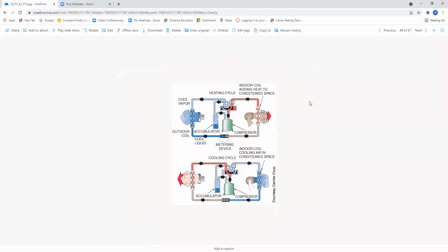Okay, in this position here, the top one shows what happens when this thing is running in the heating mode. Notice that the compressor is still going to run. Notice that heat pumps usually always have an accumulator. The idea behind the accumulator is to catch any liquid refrigerant, because we do not want this liquid refrigerant entering the compressor. Got that? We do not want liquid refrigerant entering the low side of this compressor. We have an accumulator to protect the compressor from liquid refrigerant. Notice that the discharge line, in this case, is always common to the single port on this reversing valve.